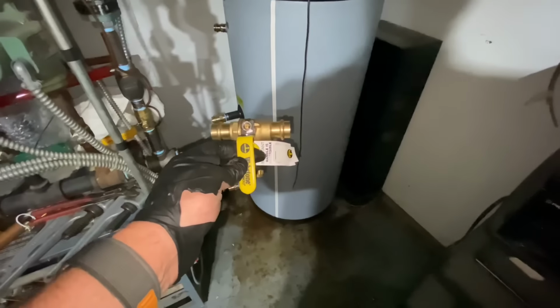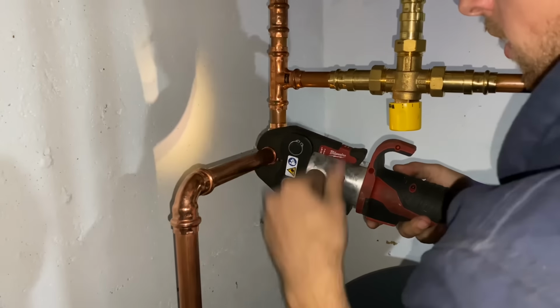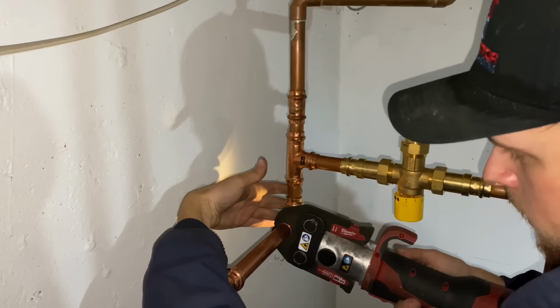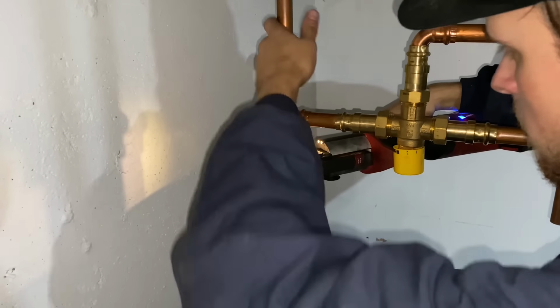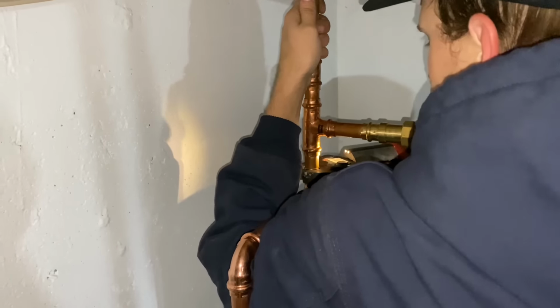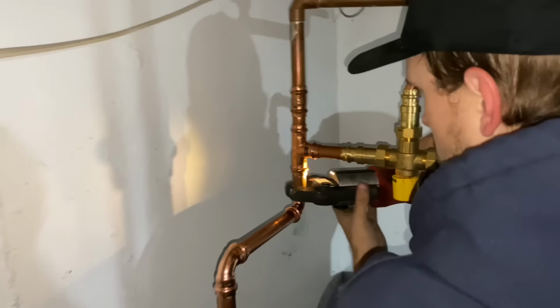Out of the inlet, we're going to take a Webstone isolation valve with drain. We're going to put that right there. That will allow us to easily drain the water heater and then come straight up, connect to my cold right here. All right, we're using the Milwaukee M18 Force Logic Pro Press tool, pressing in our cold water domestic piping fittings. Just about done, and no exaggeration, it is 9:10 in the morning.